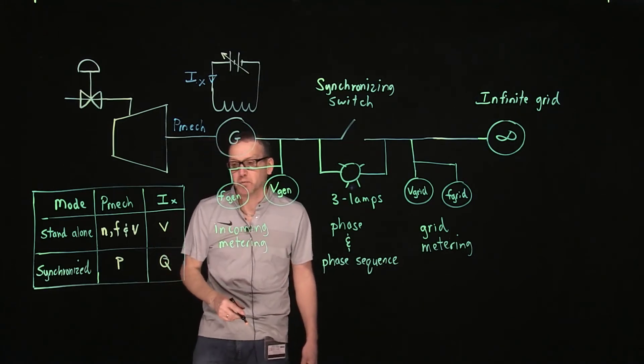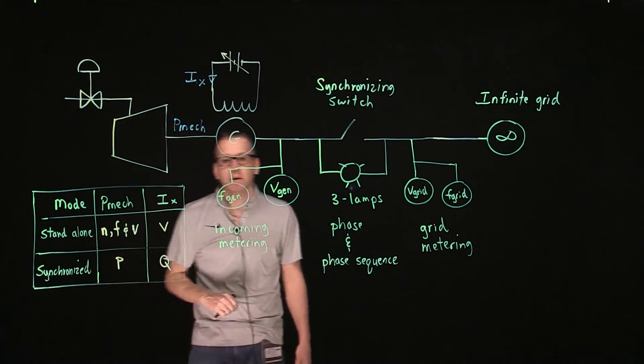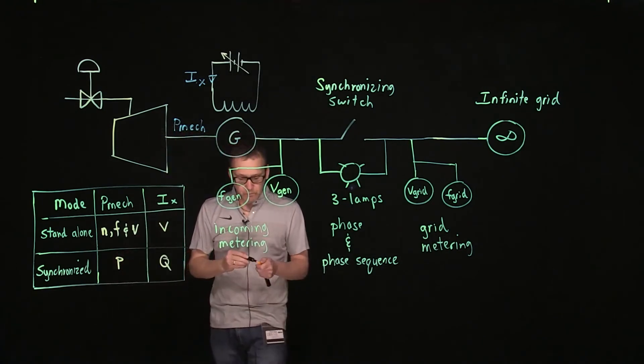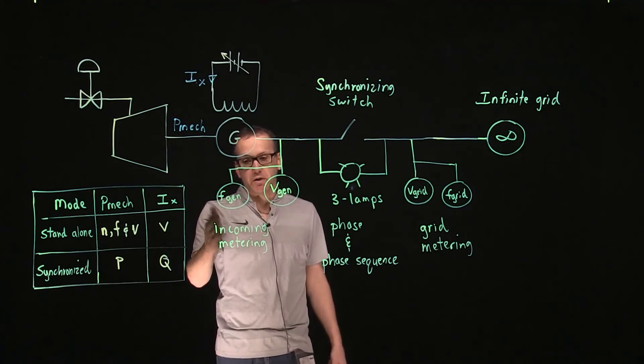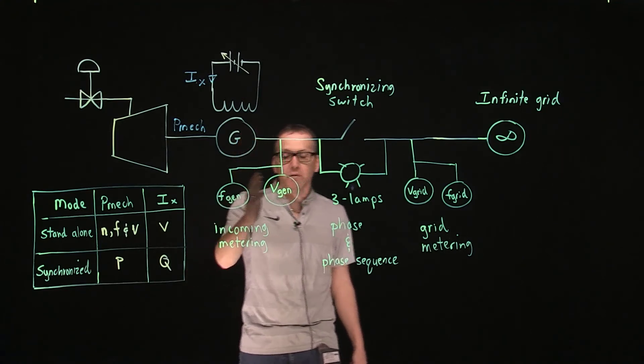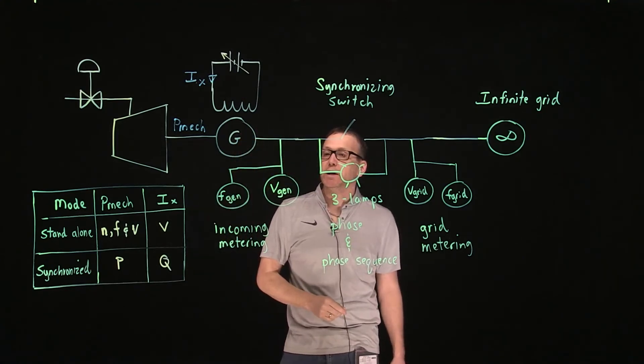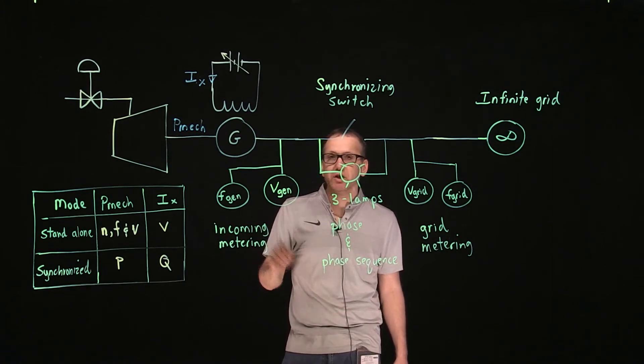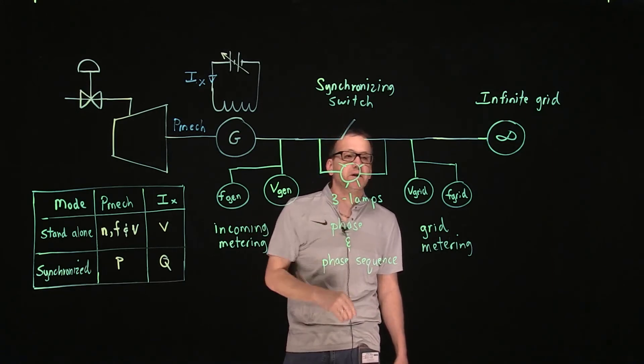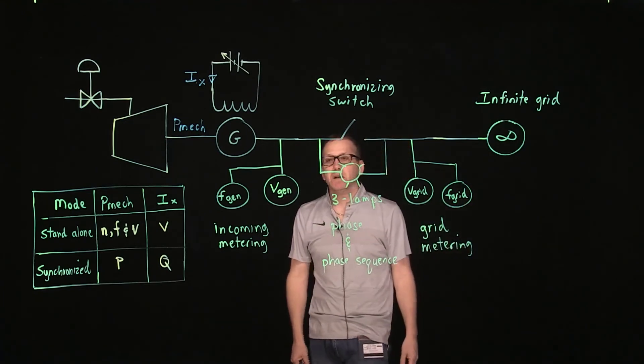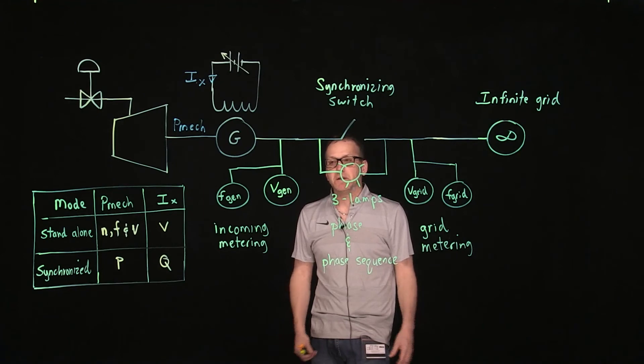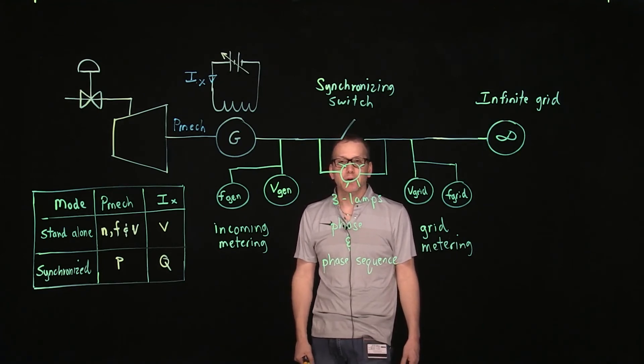The meter setup includes a frequency meter to measure the incoming frequency, a voltage meter to measure the voltage from the generator, the synchronizing switch, and two meters - one for the voltage of the grid and one for the frequency of the grid. These devices allow us to monitor all the conditions required to synchronize the generator to the infinite bus.